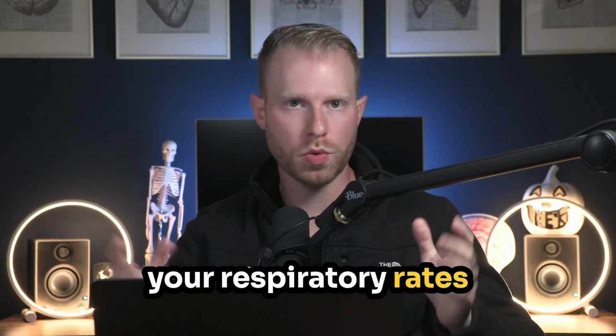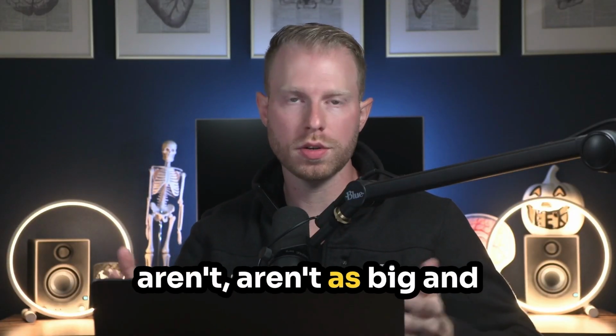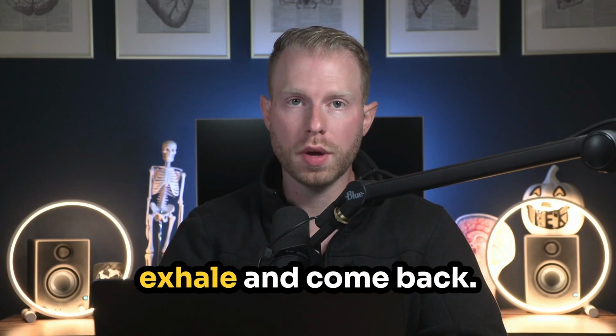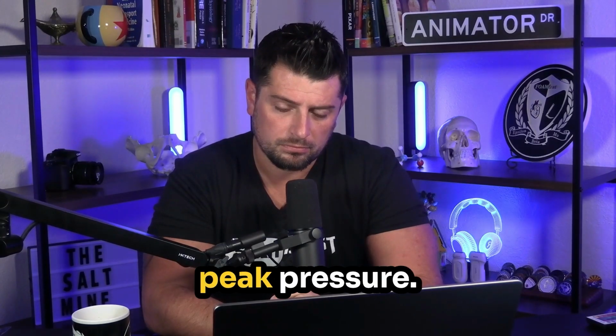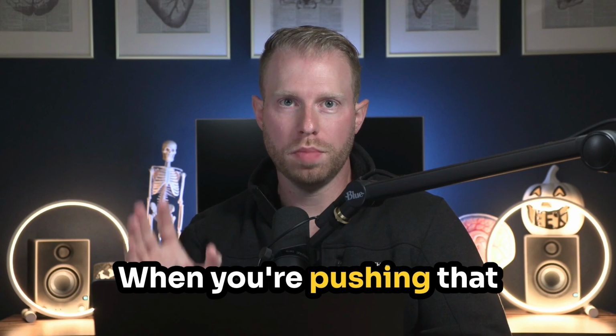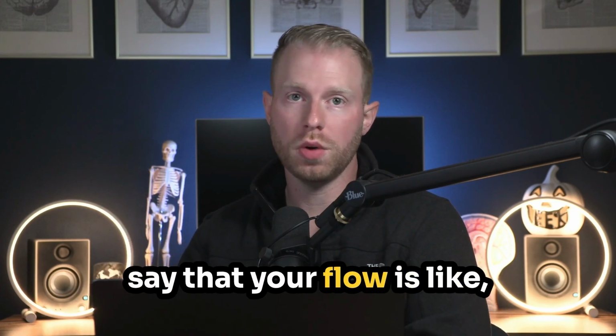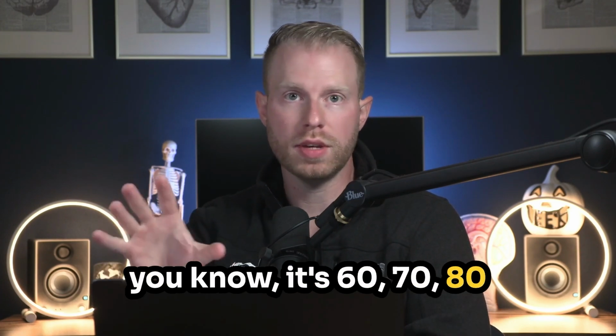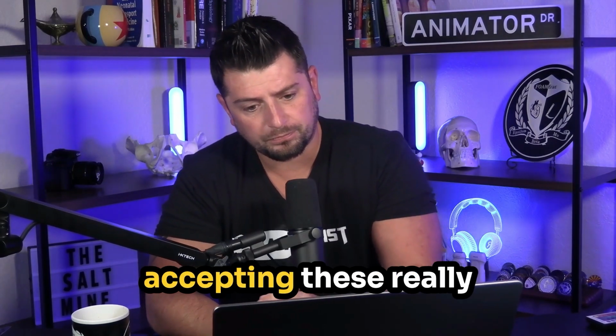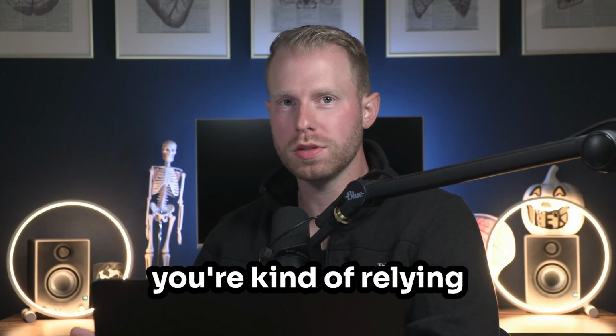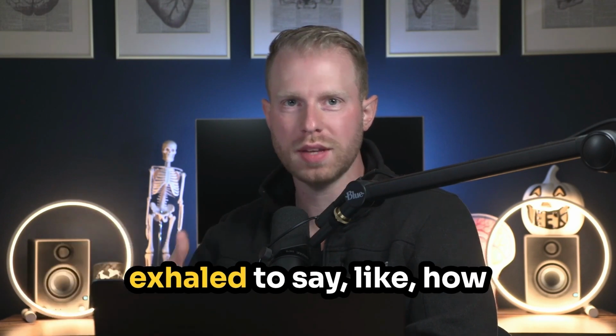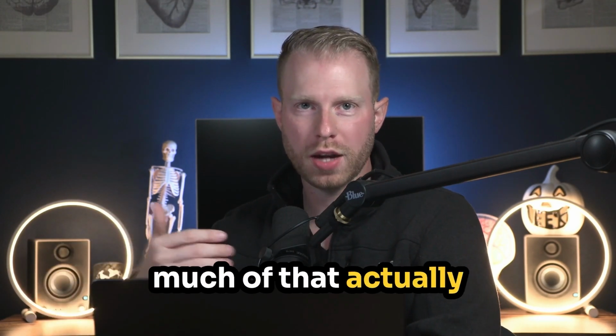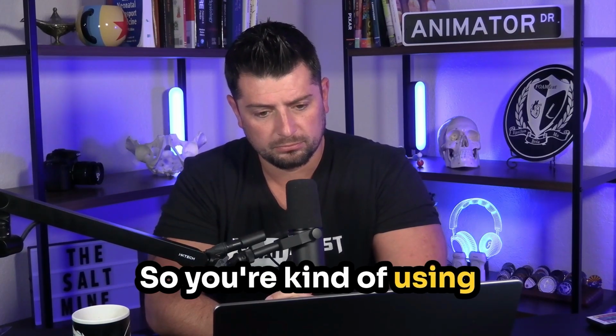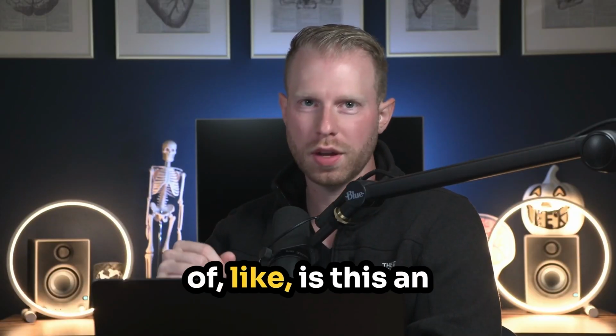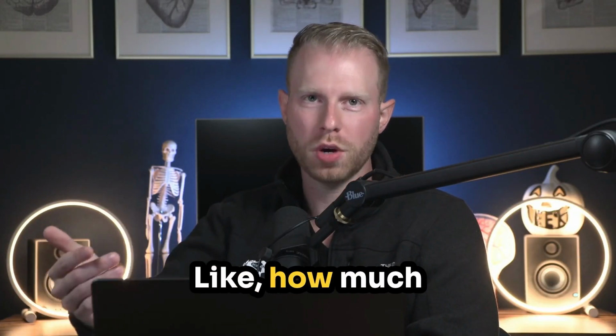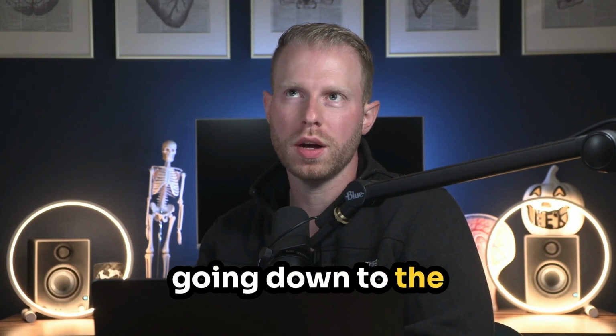And usually your respiratory rate is maybe a little bit higher, maybe your tidal volumes aren't as big, and you're just watching this tidal volume exhale come back. But with that peak pressure, when you're pushing that breath in really quick, let's say that your flow is 60, 70, 80 liters on the way in, you're accepting these really high peak pressures and you're relying on the tidal volume exhaled to say how much of that actually made it to the alveoli. So you're using that tidal volume exhaled as a surrogate of, is this an appropriate tidal volume? How much pressure is actually going down to the alveoli?